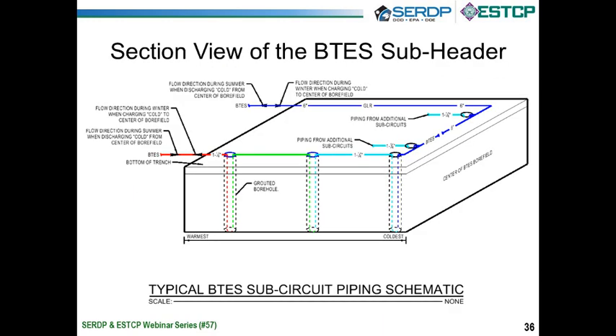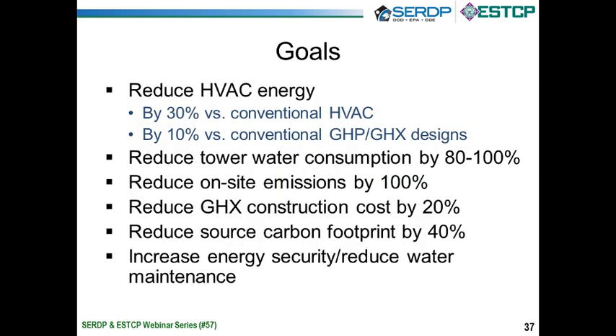With its 306 boreholes, if you do the high-level math there, 306 divided by three boreholes in series is 102. So there are 102 of these radial subheaders. In this illustration, on the left side, the red water is summertime, warm water coming in to the outer boreholes that do a better job of dissipating heat than the inner boreholes because we don't want to store the heat. They pass through the geology in the middle, cooling it further, and then the last borehole cooling it even further. Nice cold water heading back to the building. When we reverse it in the wintertime, the water's flowing in the blue main, chilling the core down, then the intermediate, then the outer, and back to the building. So that's one of the sub-circuits there and what it looks like.